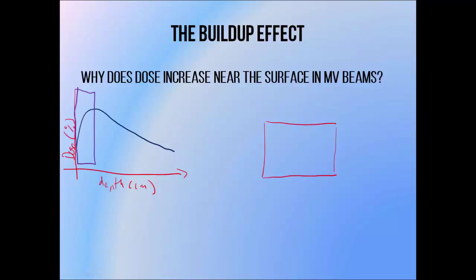When looking at megavoltage beam PDDs, we see an obvious increase in dose just beneath the surface, known as the buildup region. The first explanation involves recognizing that a photon beam turns every irradiated point within a medium into a radiation source with its own dose distribution. The dose received by a point is mostly due to the dose produced by surrounding points — from below, beside, but mostly from above. Close to the surface, there's no medium above these points in the buildup region, so these points are not receiving dose from irradiated points above, resulting in a lower dose.